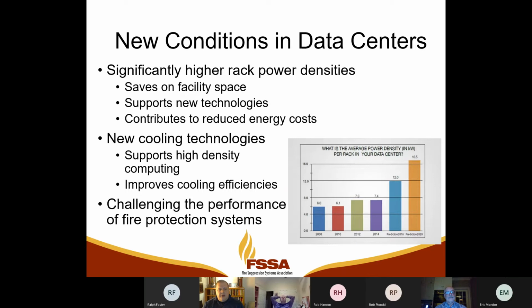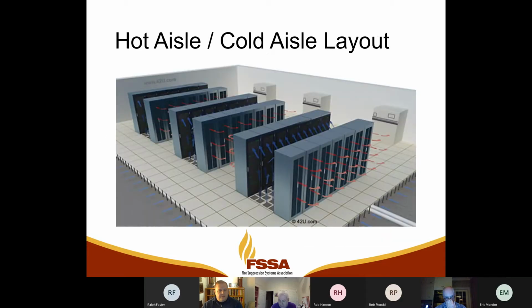is going up. So there are new cooling technologies that are being used in data centers to address these higher rack densities. That includes supporting high density computing and improving cooling efficiencies so that we get a better bang for our buck for that air that we have paid to cool. The result is it can challenge the performance of fire protection systems in those spaces, especially in older data centers where systems were put in at one time, and then over time the technology has improved and the rack densities have gone up. It can challenge, and certainly is challenging, fire protection systems.